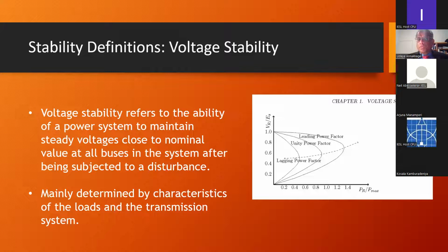That's a very important thing when it comes to voltage stability, because under highly stressed situations, if the reactive power supplying devices like static VAR compensators, STATCOMs, even synchronous generators with excitation control, reach the maximum limit, then the nearest voltage control point to the load will be moved to a further away point in the grid, increasing the electrical distance between the load and the voltage control point. That will decrease the maximum power transfer capability. So these things need to be considered when you evaluate a power system operation to see if it is voltage stable.